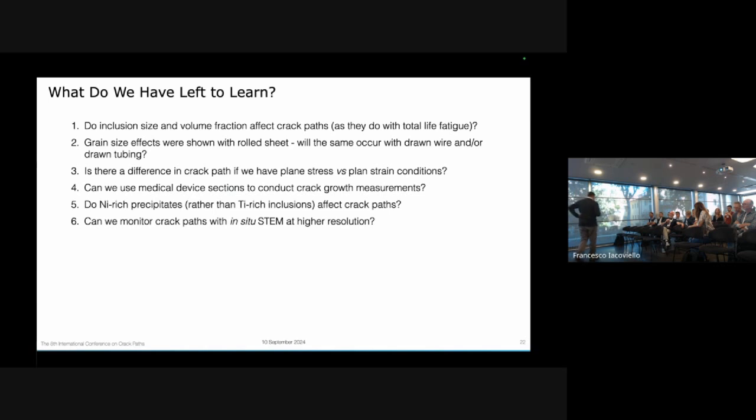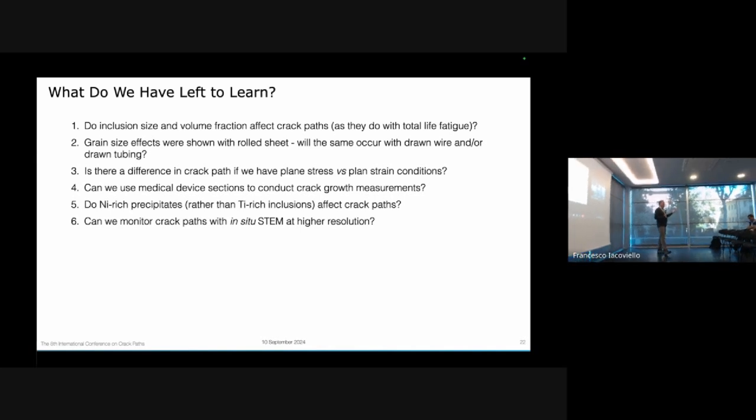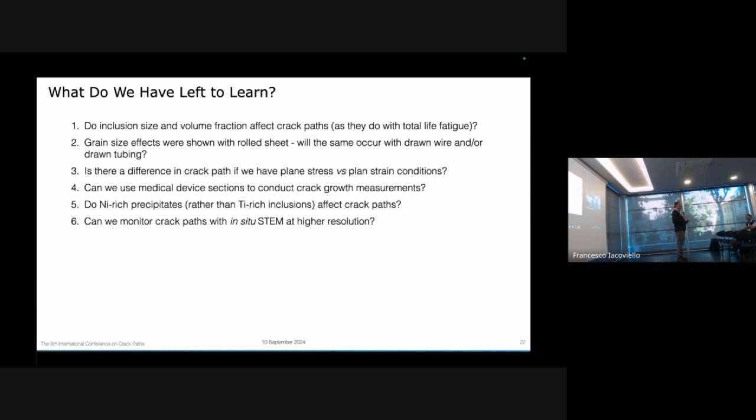Great question, as always. So the question about inclusions. So let me take you back when I was a young lad, real young lad, 150 years ago, when I started in the field. And we had oxygen contents in our nitinol that were something like 1,000 parts per million. Okay? We're now down to less than 400. We have improved. Okay? We now have material that have inclusion sizes that are like 2 microns. Instead of the ASTM standard, ASTM F2063 allows us to have 39 micron inclusion size.